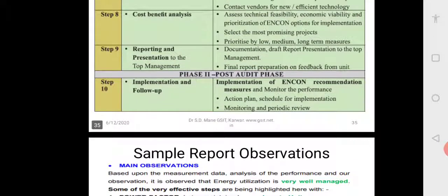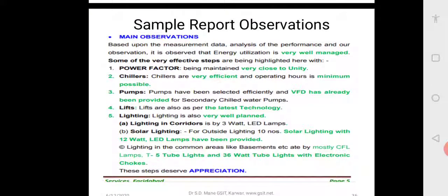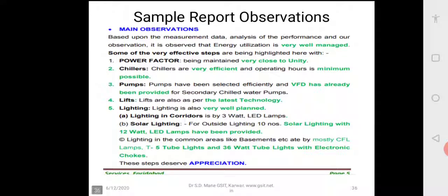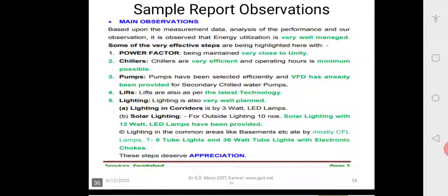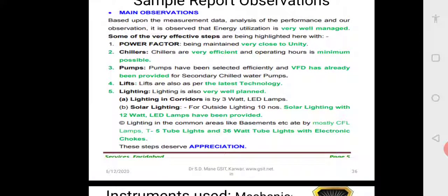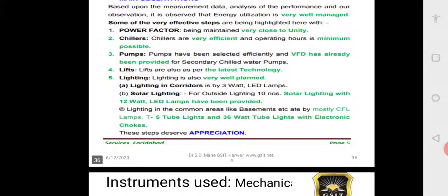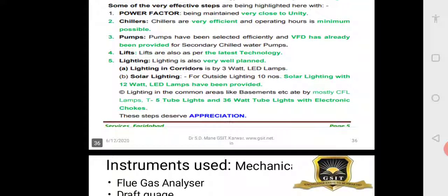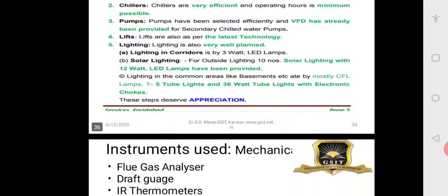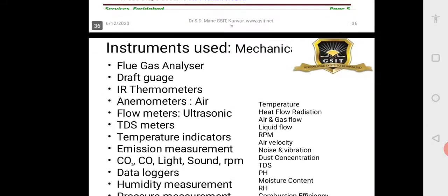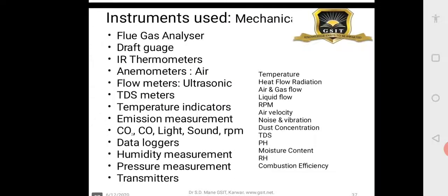One report observation I wanted to share: a new mall in Faridabad was recently audited. The main salient points are that the power factor is being maintained almost at unity — very good. Chillers are very efficient, pumps are high-efficiency, and VFD has been introduced. Lifts are new technology, lighting is good LED lamps. The only suggestion was to replace 36-watt tube lights with electronic chokes with LED lights. When all new technology is already used, there is very little scope for further conservation.